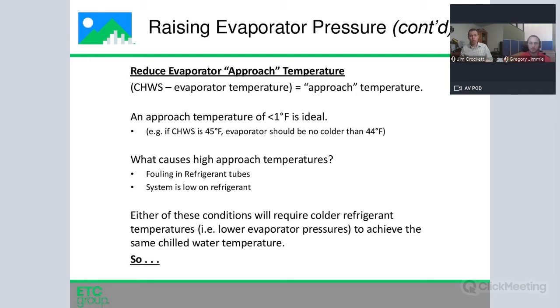Another way is to improve your approach. When the system is running well, the temperature of the chilled water leaving the chiller is within a degree of the evaporator temperature. So your cooling cycle has your refrigerant down at 42 degrees. You should be getting 43 degrees out of your chilled water system. But what if something happens to compromise the approach? By the way, approach is the difference between refrigerant and supply. If somehow approach were 5 degrees instead of 1 degree, if you want 43 degree chilled water, you need to take your refrigerant down to 38 instead of down to 42. You have to do a substantial amount of additional work. Your compressor has to work quite a bit harder.